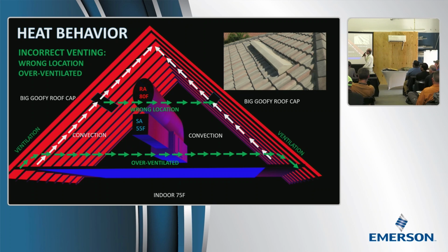So what I recommend you do when you find this, how many times is the air handler right next to that thing? Right? The air handler's right there, and there's the big goofy roof cap blowing cold air on this cold cabinet. Why wouldn't this sweat? So anyway, put your data logger in that space, take some duct board, go buy some dust masks, seal these off, and watch it stop sweating. Simply because you took the moisture away. You dammed it up. You're not letting the moisture get to the duct.